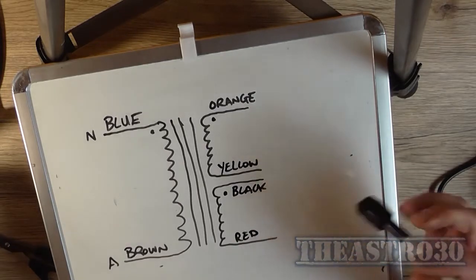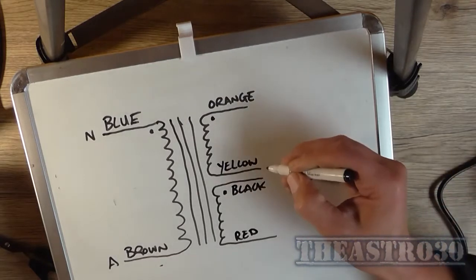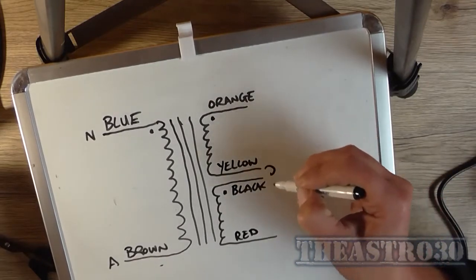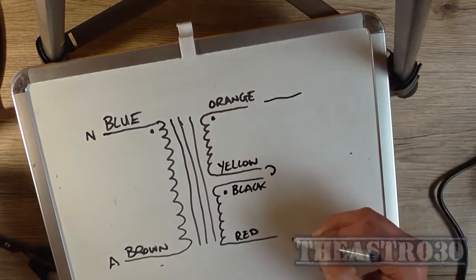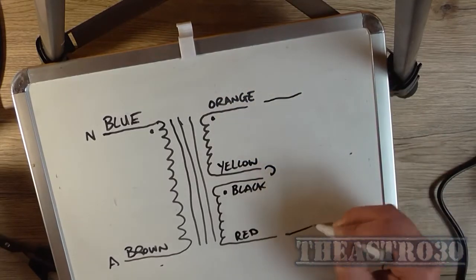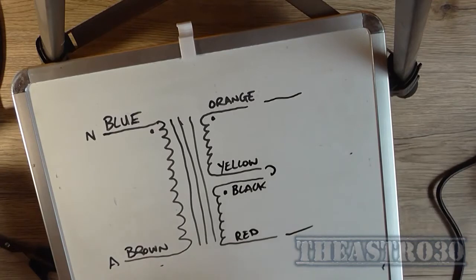But if we're going to be putting it in series, which is what I'm doing, the black would go to the yellow, orange would go to one side of the AC connection, and the red would go to the second side of the AC connection on the board. So that's how it's going to be wired.